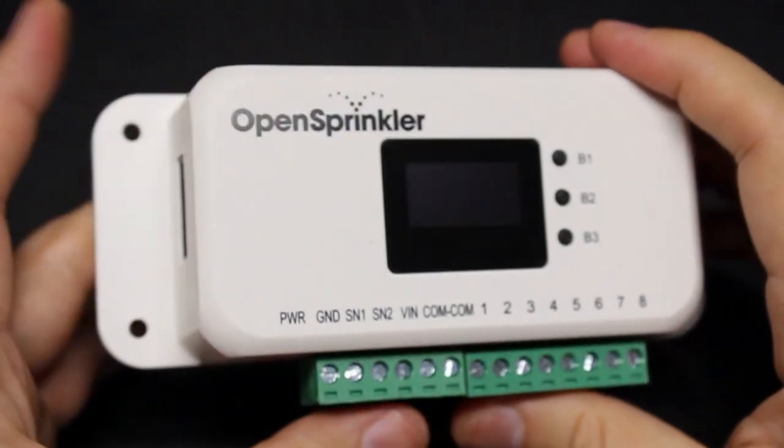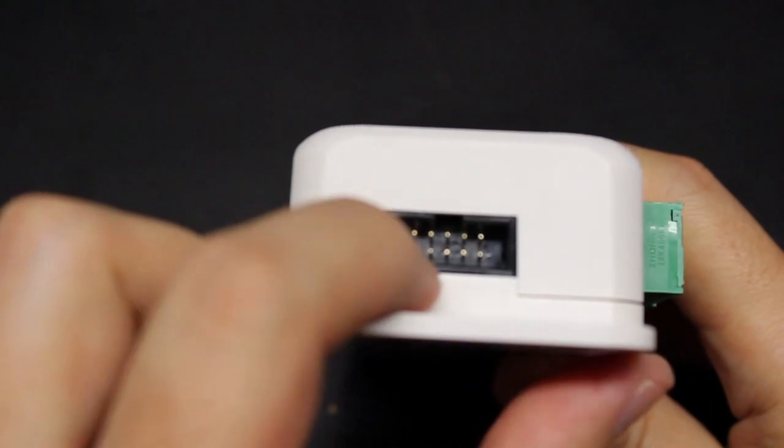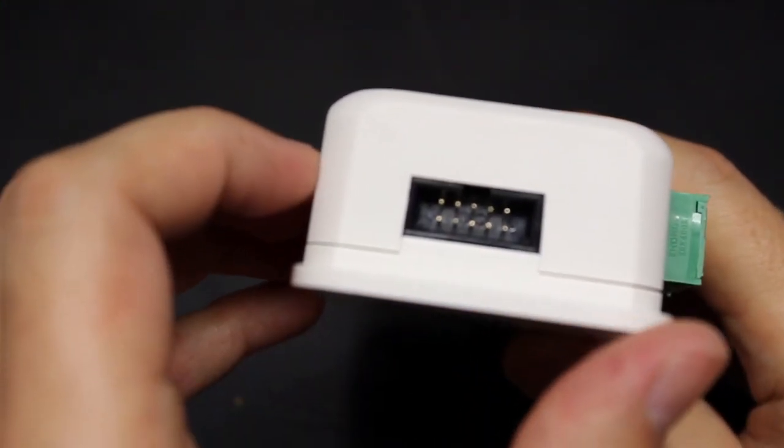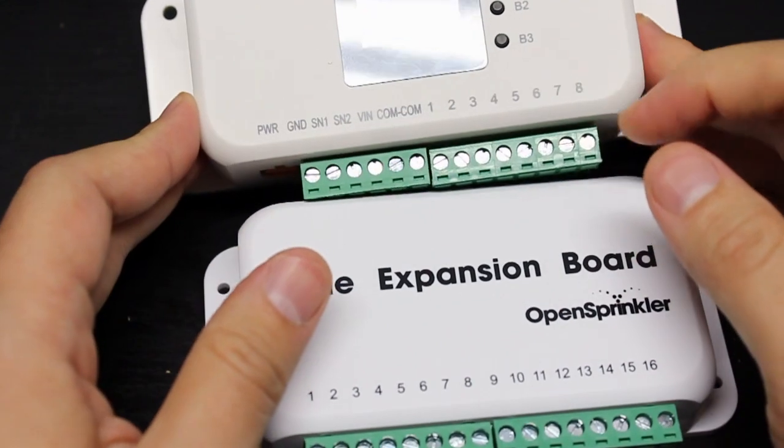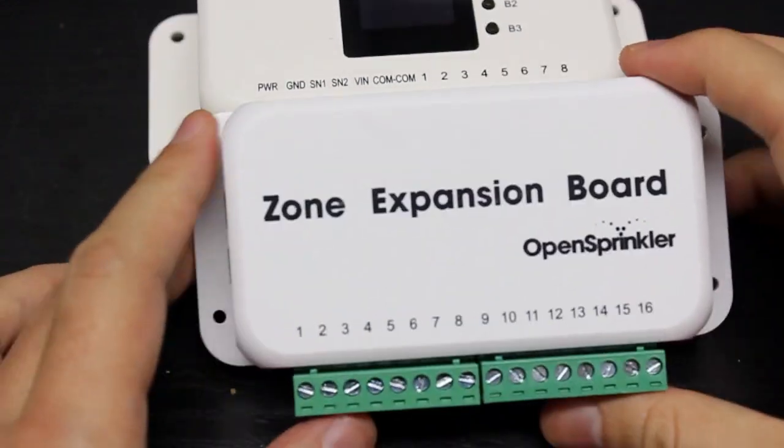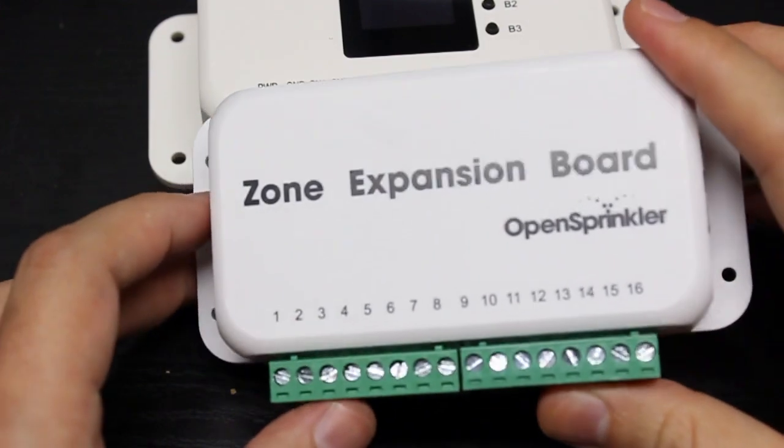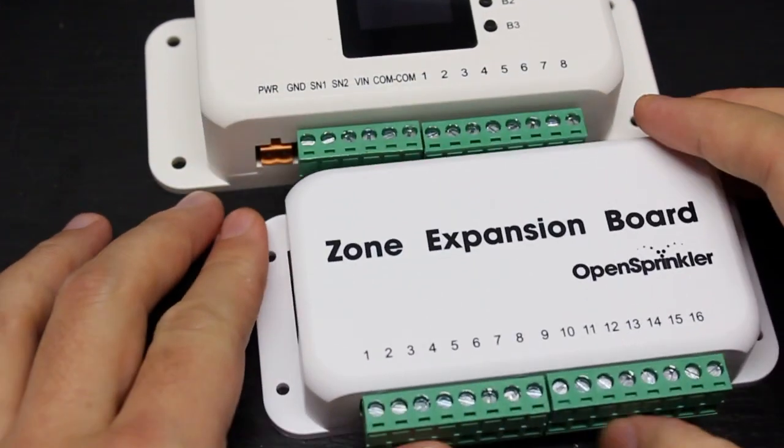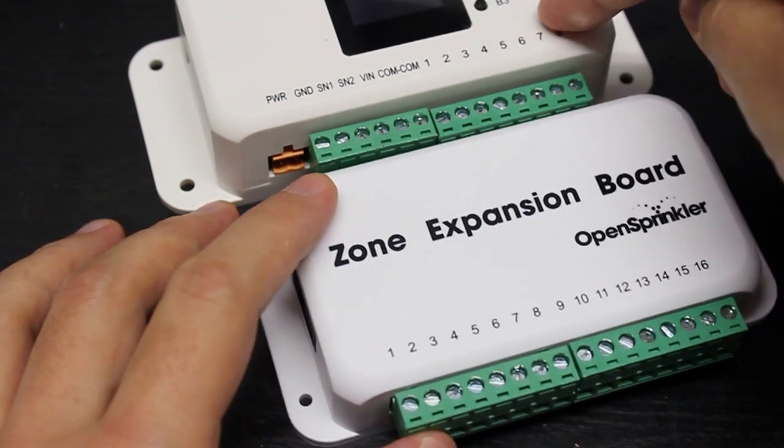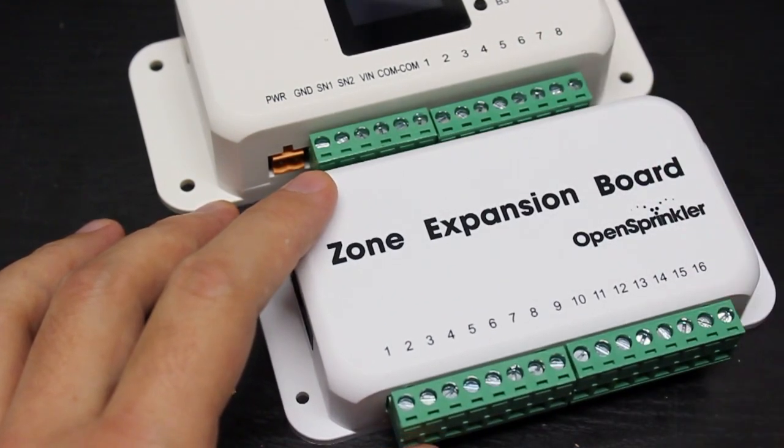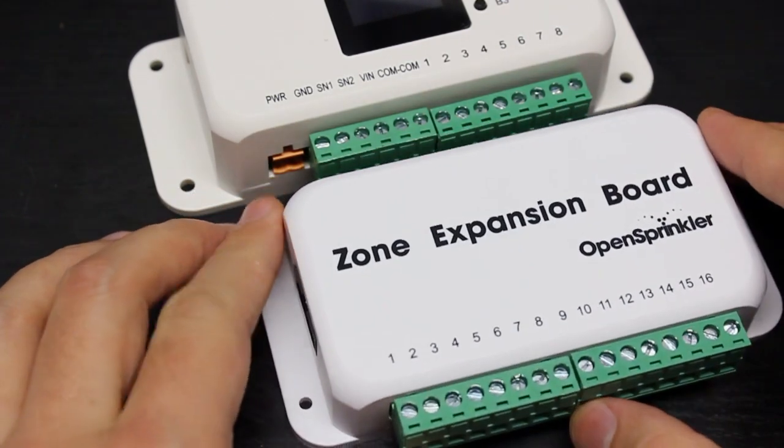Next, on the left side of the controller is a 2x5 pin connector. This is the expander connector. If you want to expand the number of zones beyond 8, you can purchase expanders. Each expander adds another 16 zones. At the moment, you can chain up to 4 expanders. So including the main controller and the 4 expanders, you can have up to 72 zones in total.